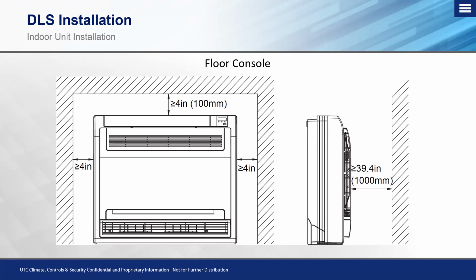This is where you're going to access your coil, your filters, and then more importantly, your electrical section to do any installation work, or on the post-sale side, coming back for service work, depending on if there is an issue with the system or not. So we need to maintain at least 40 inches of space so that can properly open and close so that we can get in there and service that equipment. And of course also too, to make sure that we can get the proper return and supply. And you can see on this one, return is coming in at the bottom, discharging at the top.